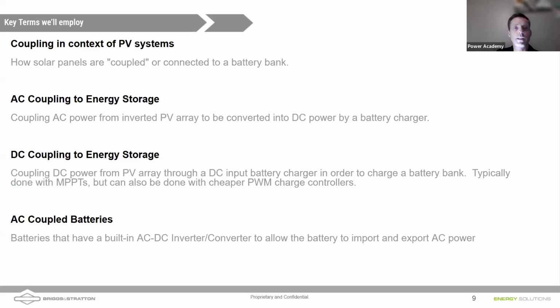That means taking that existing solar, which already has either a string inverter or microinverters on it, and running that through an inverter that's capable of charging a battery. In the previous example, I showed this being done with a solar converter. Not all inverters are capable of operating with batteries. And even some very popular inverters, like SolarEdge inverters, are capable of using batteries, but they're not grid forming. What does that mean, Daniel?